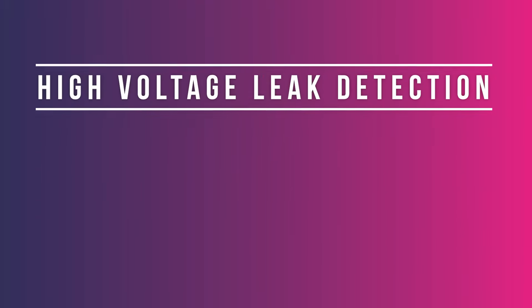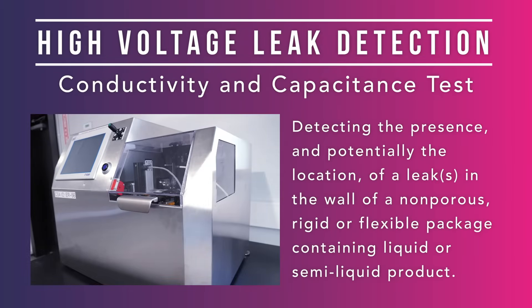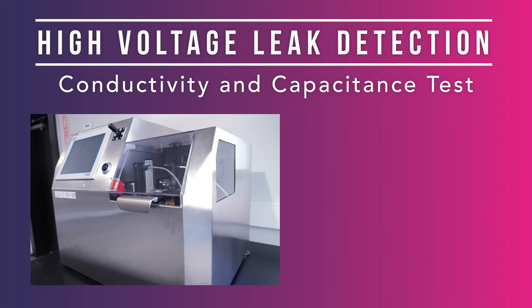High voltage leak detection, also referred to as the conductivity and capacitance test, is an approach for detecting the presence or potentially the location of a leak in a wall of a non-porous, rigid, or flexible package containing liquid or semi-liquid product. Numerous instrument parameters, and therefore method parameters, exist which must be optimized.